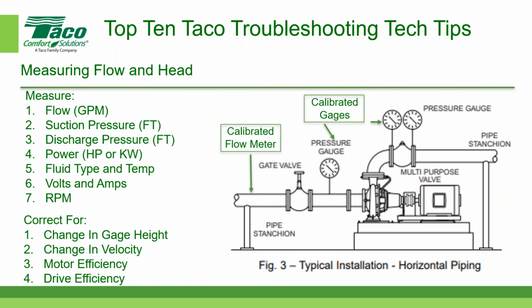All right, so here are some of the things to look at when we're asking for measurements, as I have here on the left-hand side. Well, that data sheet that you can download, it's a downloadable document. Okay, so we're asking for this information: the flow in gallons per minute, the suction pressure, the discharge pressure, the power, the horsepower, the kW, and if you don't have that data directly, then you'll have to take the volts and the amps and do all those calculations that we talked about.